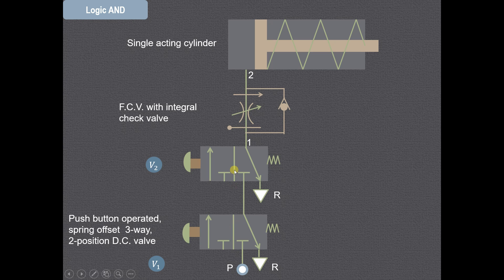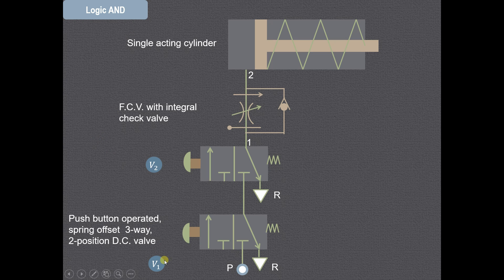In the logic AND circuit, similar two valves are used but they are connected in series. These are again push button operated, spring offset, three-way two-position direction control valves shown in the right envelope mode. The pressure port P is blocked and therefore nothing will happen — both valves are in the off position. When both valve V1 and valve V2 are operated and in the on position, we get the left envelope mode, and then and only then we will get the operation of the single acting cylinder. This is known as the logic AND circuit. Both V1 and V2 are required to be in the on position.